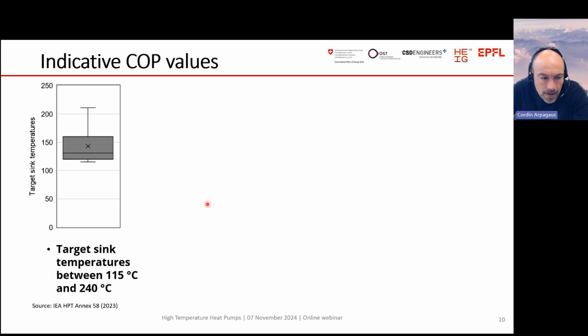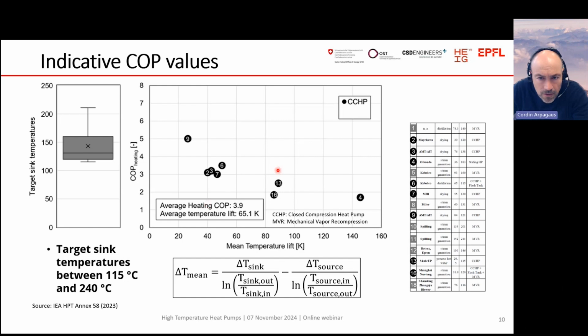The COPs, we have some COP indicative values shown here. For the closed cycle heat pumps, the COP follows such a line as a function of the mean temperature lift. And for these different examples of demonstration cases, when you look at MVR cases, they achieve higher COPs than the closed cycle heat pumps. On average, these cases have a temperature lift of 65 Kelvin and a COP of 3.9.